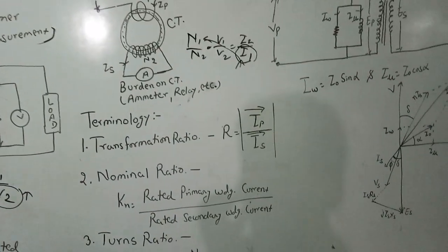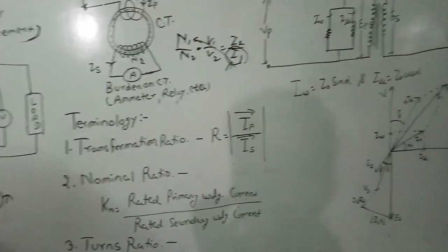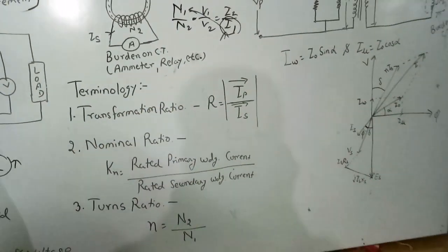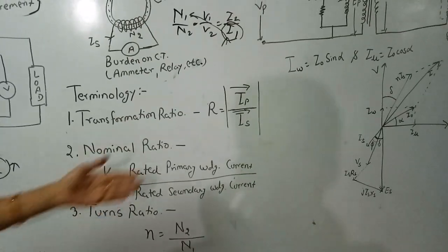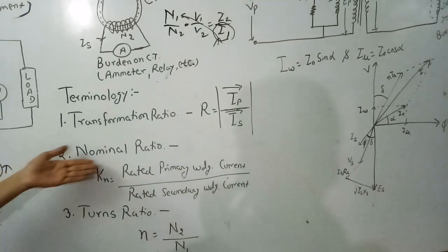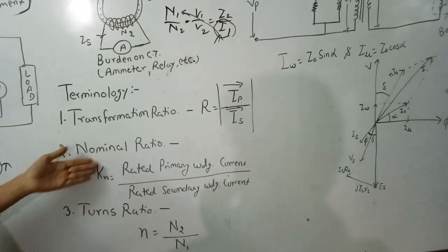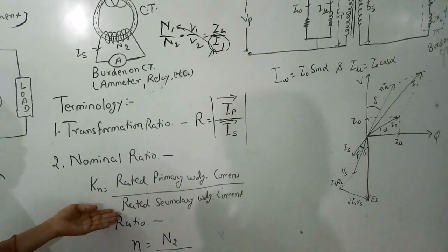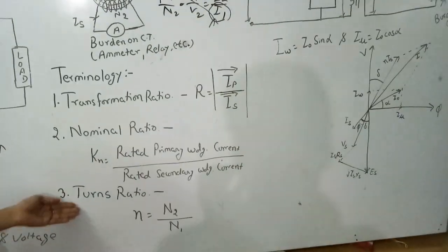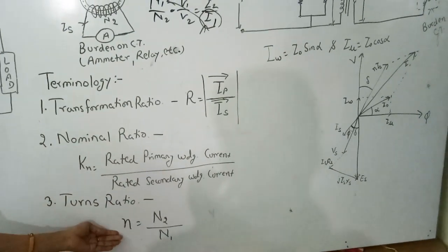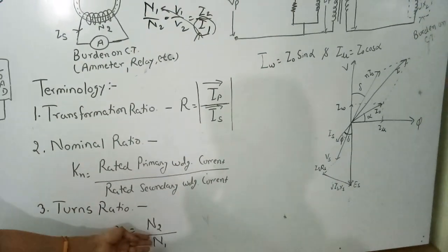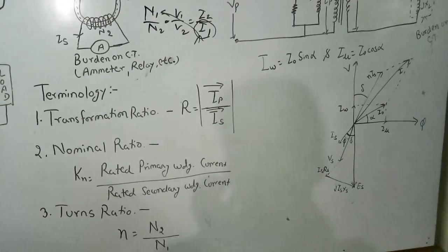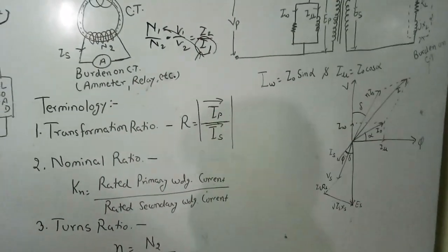There are several terminology terms used in current transformers. First is the transformation ratio, defined as the primary phasor current to the secondary phasor current. Second is the nominal ratio, defined as the rated primary winding current to the rated secondary winding current. Turns ratio is denoted by small n and equals N2/N1, which is the actual number of turns in the secondary to the primary winding.